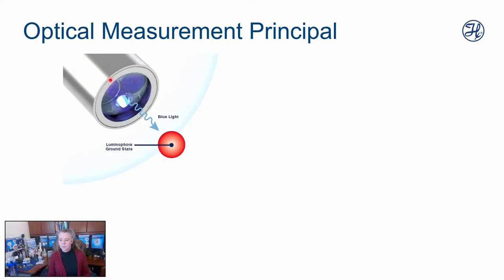Inside of the probe, if you take the cap off, there is a laser. LED lasers nowadays are low charge, low heat and low power, but the laser emits a light. It's a blue light. That light comes out of the laser and goes inside this cap. Inside of the cap, there's absolutely nothing. At the end of the cap, there is a hard layer of glass. On the outside of the glass, there's a luminophore. And on the outside of the luminophore, there's silicone.